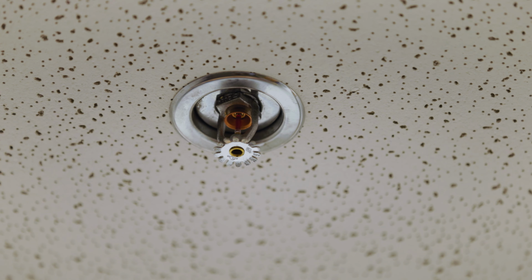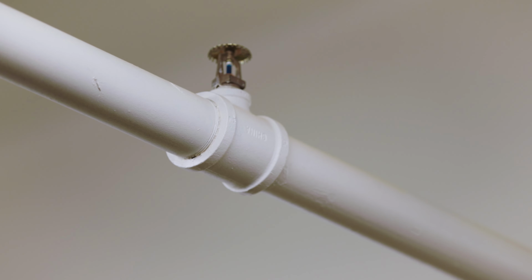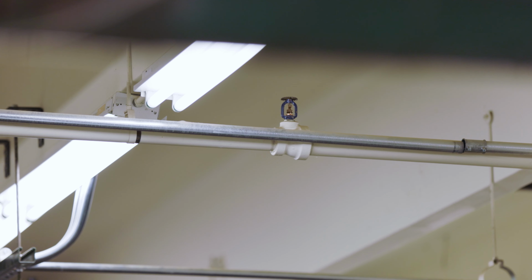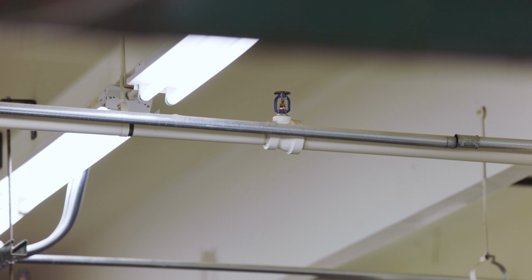We've discussed sprinkler systems only in the fact that we talked about the riser and some of the elements that you'd see in the main part of the sprinkler system. But as far as the CommSop goes, we're supposed to look at the sprinkler systems visually from the inside. A couple of key aspects when looking at the sprinkler is first, making sure none of the heads are obstructed. Next, making sure they're not otherwise painted from the factory.